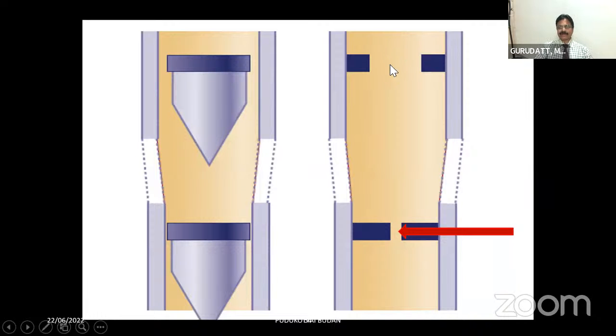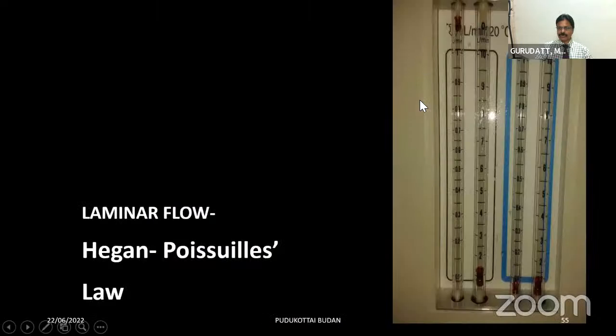So it is like an orifice. So here the flow is orificial. One thing you should realize: orificial flows are always turbulent, tubular flows are always laminar. So for low flows, it is laminar flow. For higher flows, it is turbulent flow. Again, why should you know about this? When you are using low flows, because it is laminar flow, it obeys Hagen-Poiseuille's law, and Hagen-Poiseuille's law says the flow is inversely proportional to the viscosity. Since the viscosity doesn't alter with altitude, the flows will remain whatever flow you have set, as far as low flows are concerned.